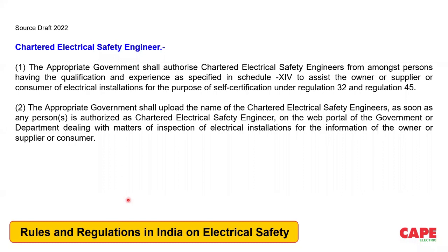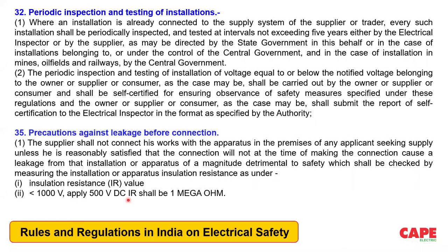Also, the regulation, I think the number is 6, talks about the chartered electrical safety engineer. Who is a chartered electrical safety engineer? What is his qualification criteria, and what kind of formats does he have to follow? For example, what kind of tests does he have to do? He has to do tests as per regulation 32, periodic inspection, and periodic inspection means every 5 years you have to do the testing prescribed in this particular regulation.